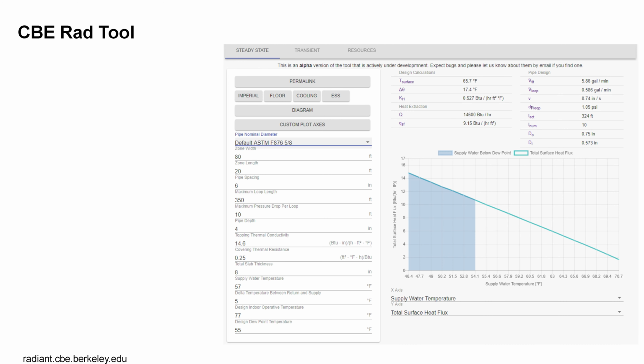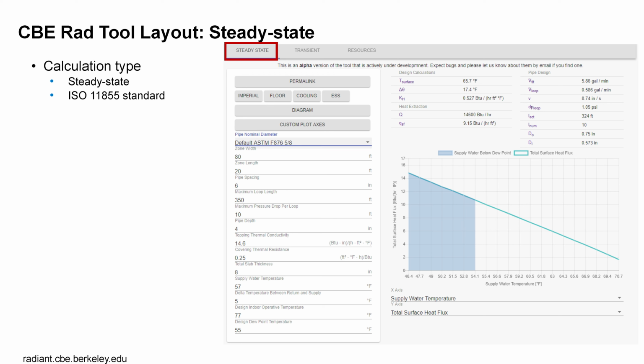So the third tool is the CBE RAD tool. It's an interactive design tool for the early design of high thermal mass radiant systems. The primary aim of this is to provide an interface for estimating the performance of high thermal mass radiant systems under steady-state conditions for both heating and cooling, and transient or dynamic conditions on the cooling design just for the cooling aspect. The steady-state conditions are based on the ISO standards, which is standard practice for many building designers, and this tool facilitates those calculations.